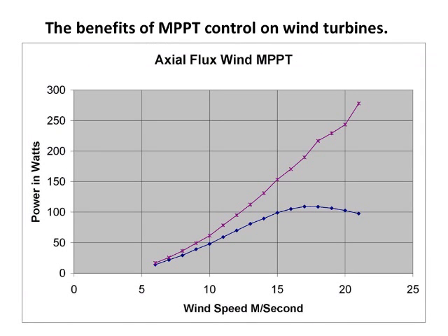MPPT for wind. MPPT can greatly enhance the function of wind turbines as well. The typical installation of a wind turbine has the turbine wired directly to the batteries and a diversion controller off the batteries. The problem with this, as shown in the graph, is the turbine's RPMs are then held down by the battery voltage. The turbine's blades are designed to run at a ratio proportional to wind speed. This is called TSR, or tip speed ratio. When hooked to the battery, the turbine will only be at its optimal TSR at 1 wind speed and effectively stalled above that speed.